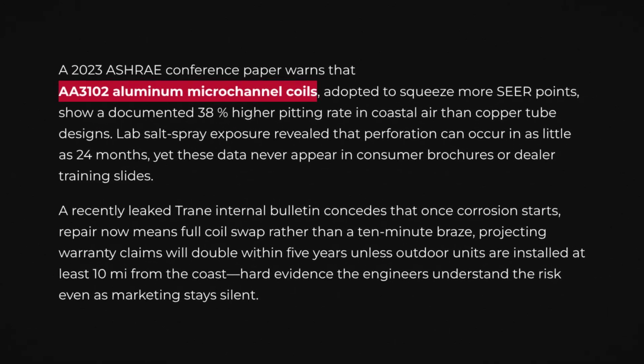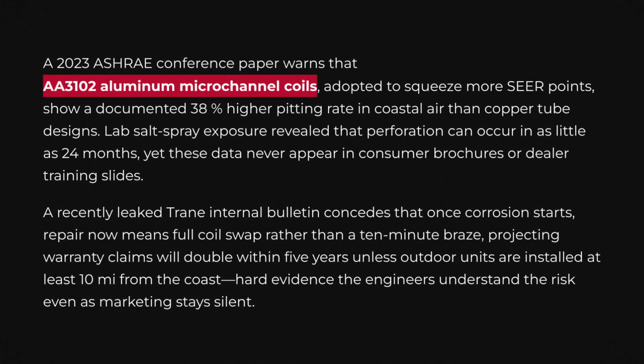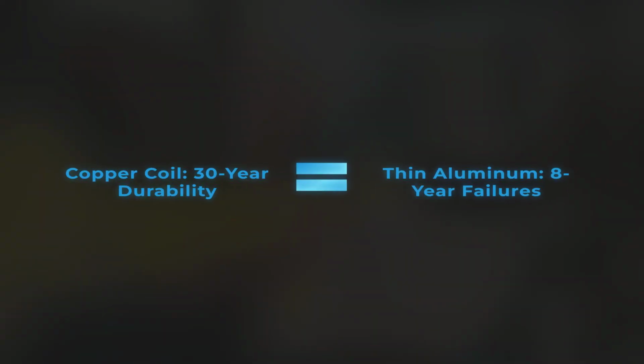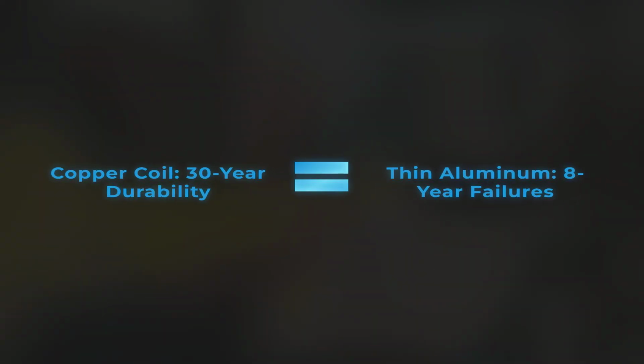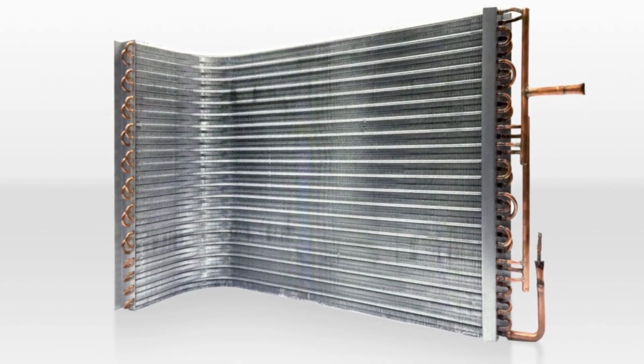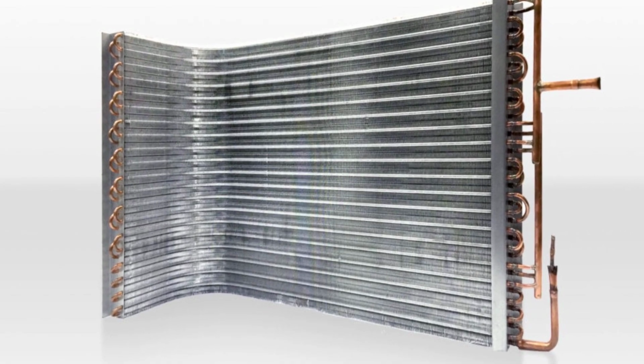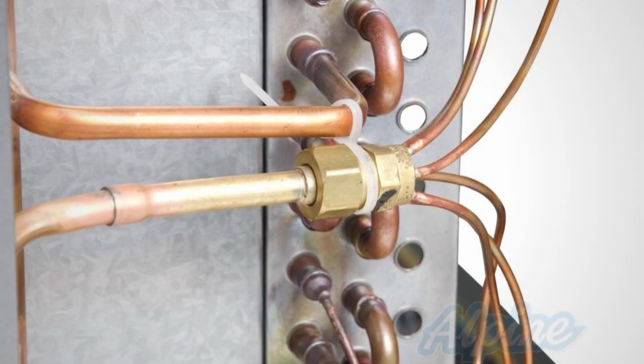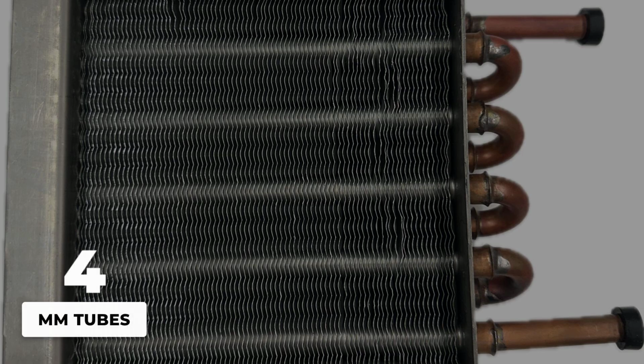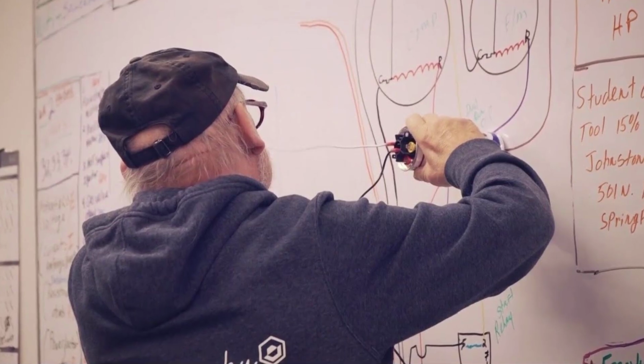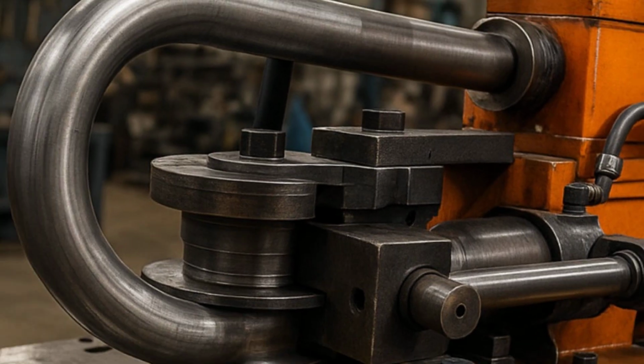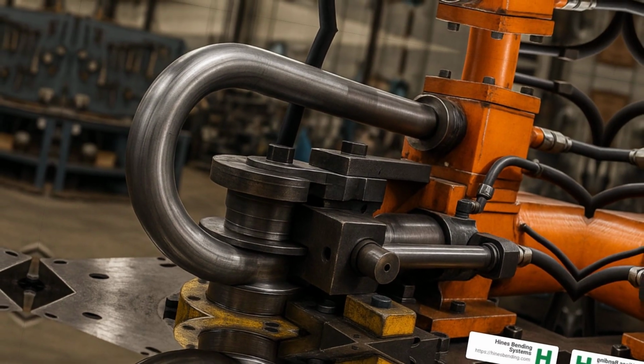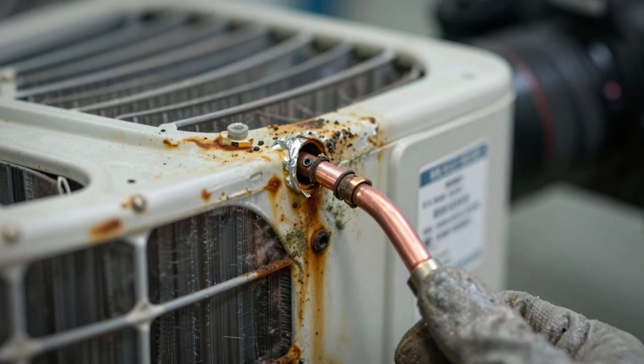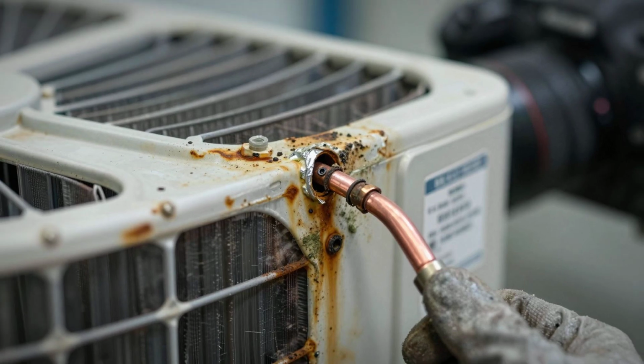ASHRAE conference literature notes that AA3102, the aluminum alloy used in extruded microchannels, has recognized atmospheric corrosion concerns in HVAC applications. The engineers know, the brochures do not mention it. Second, the copper that remains. Some systems still use copper tubes in the indoor evaporator coil, but those tubes got smaller too. Goodman specs 5mm copper tubes with enhanced aluminum fins on several current heat pump models. 5mm. That is not overbuilt margin. That is optimization math. Just enough material to hit the efficiency target, just thin enough to save manufacturing costs, and just fragile enough to develop pinholes when corrosion or contamination finds a weak spot over time.